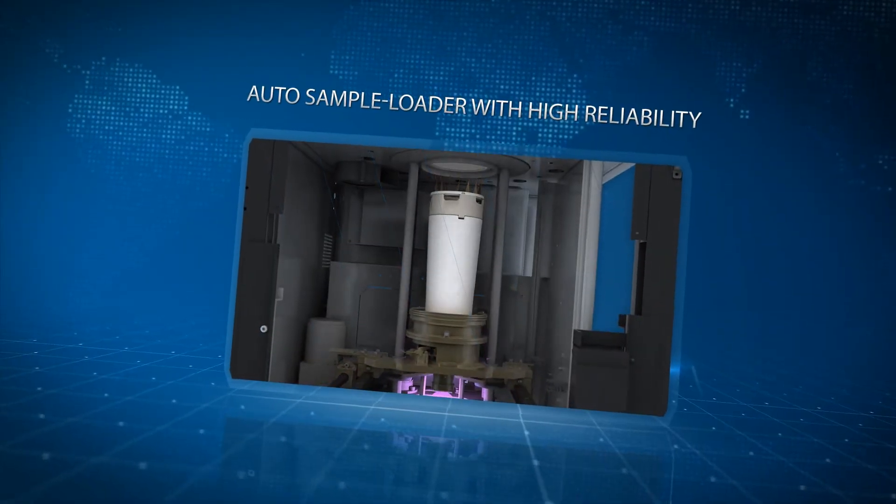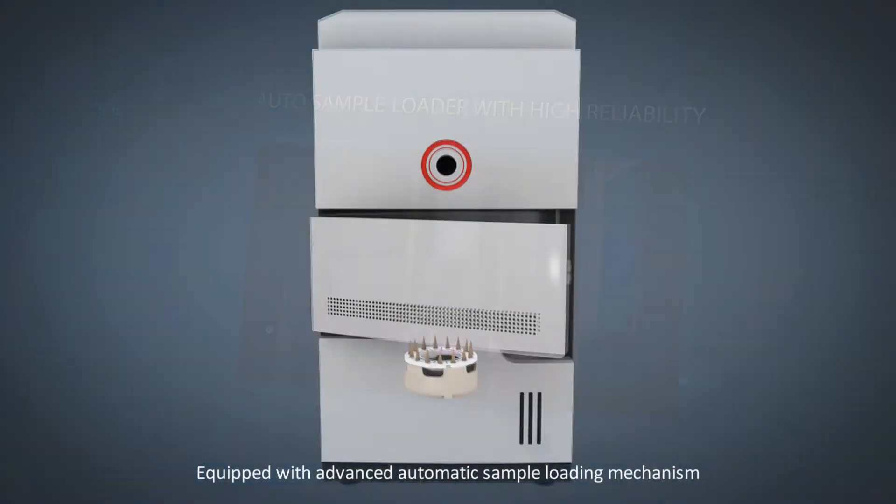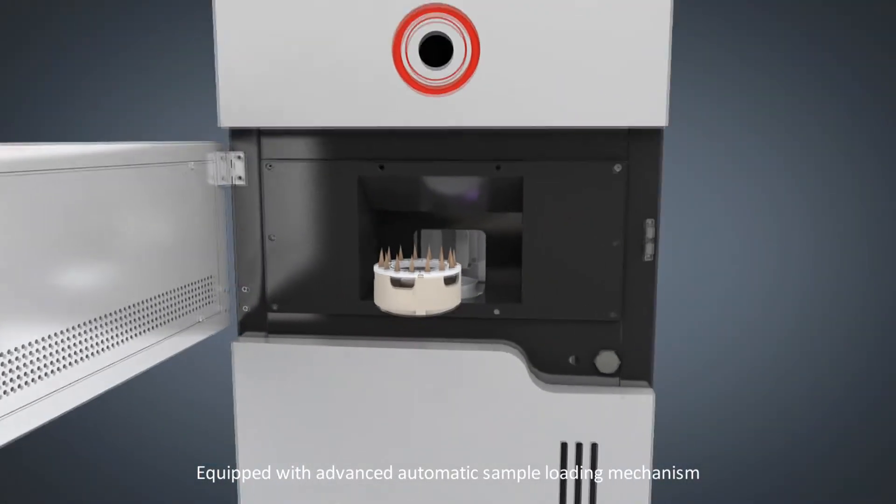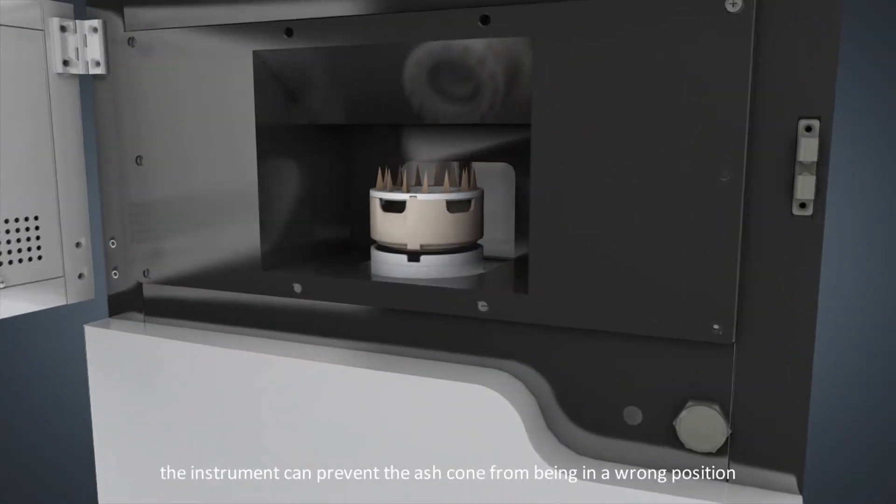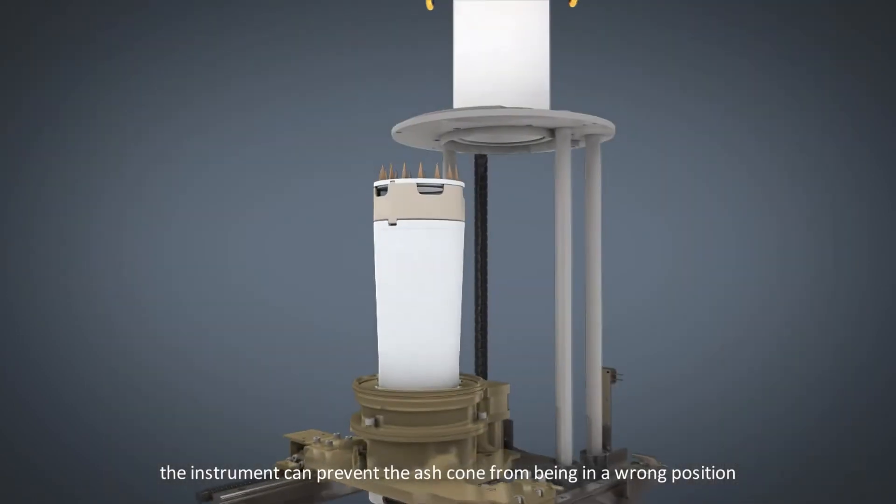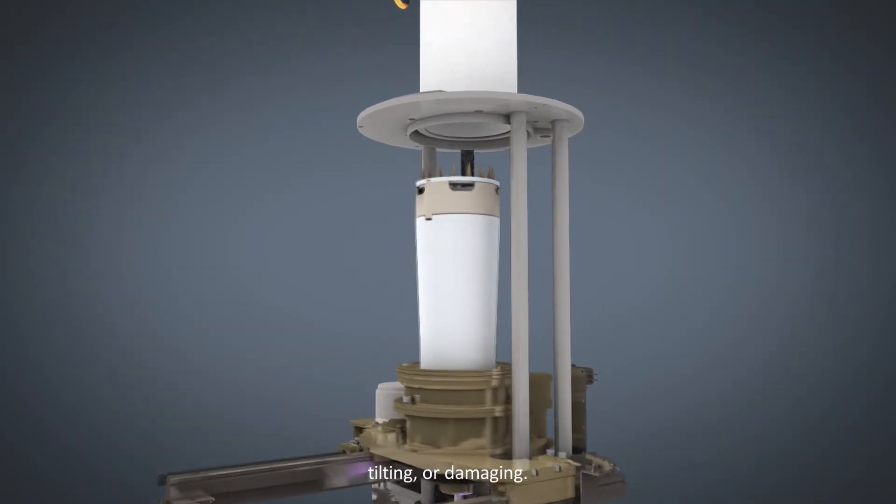Equipped with an advanced automatic sample loading mechanism with high reliability, the instrument can prevent the ash cone from being in a wrong position, tilting, or being damaged.